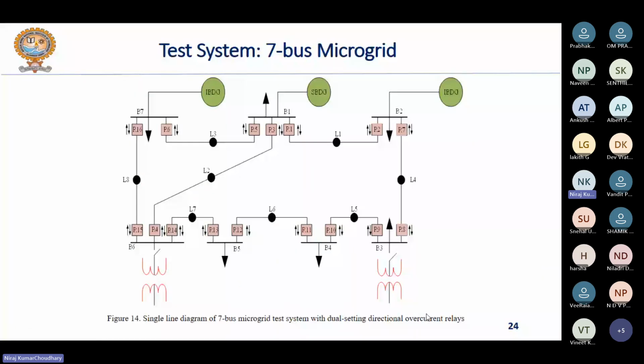Now the test system considered for this study is a 7-bus microgrid system, which is basically a part of the low voltage part of the IEEE 14 bus benchmark system. Below this transformer, the upstream network of this system is your high voltage section. That's why we have not considered that section for the study of the relay coordination problem. We have only considered the low voltage section of the IEEE 14 bus benchmark system. And here we have modified this system as per the connection or integration of DGs. We have integrated two DGs and one SBDG in the system at three suitable nodes.